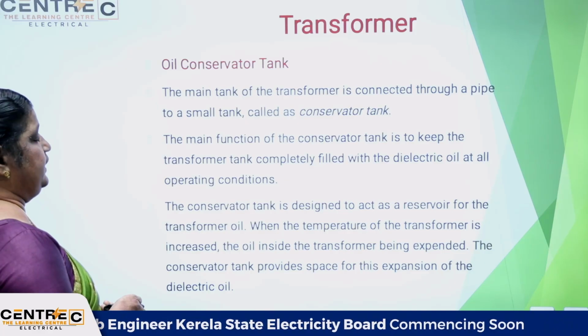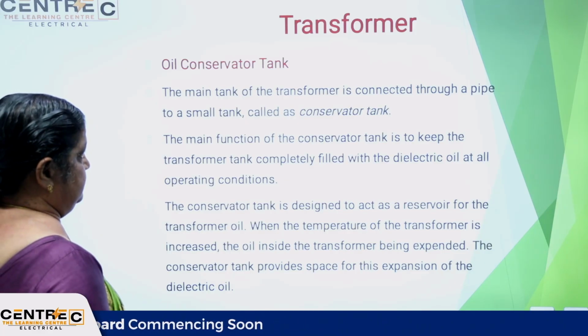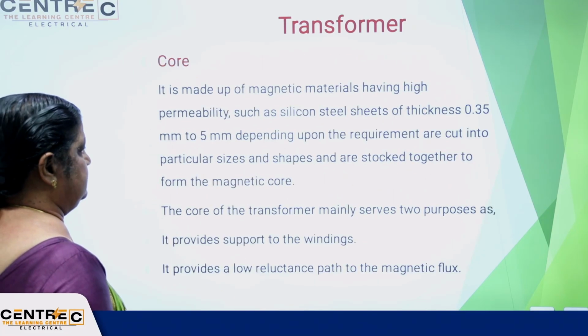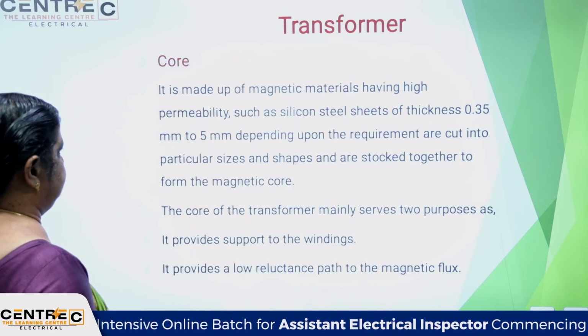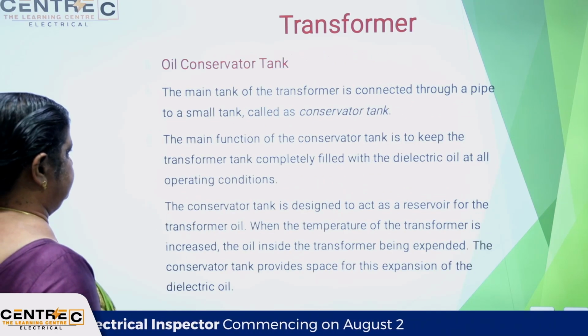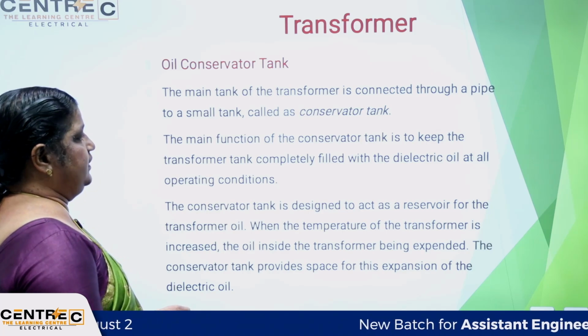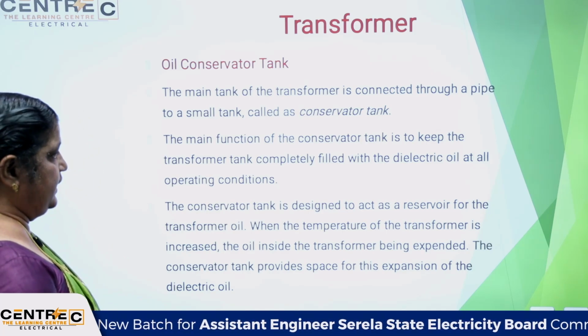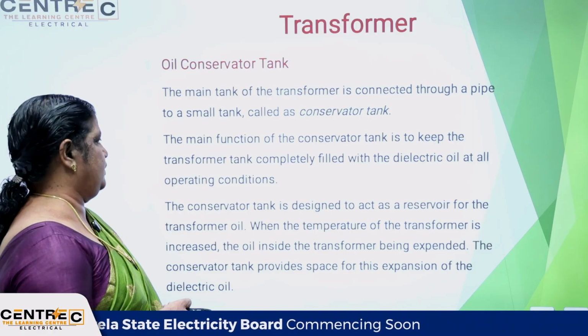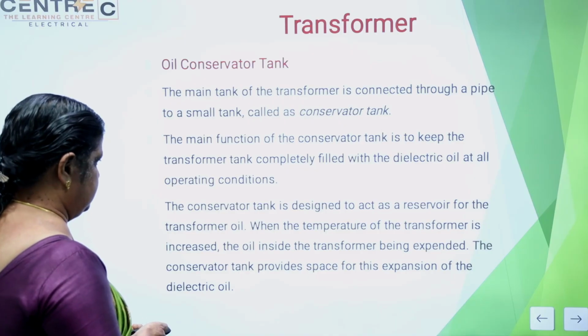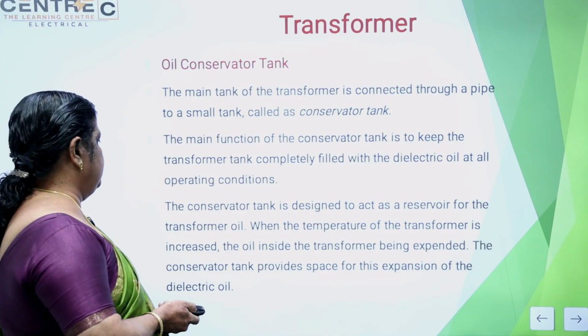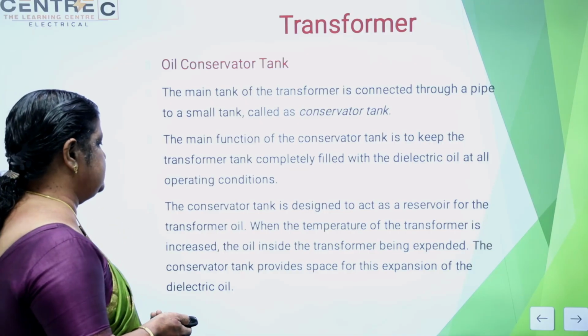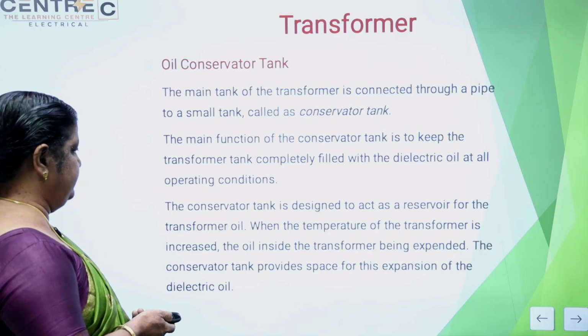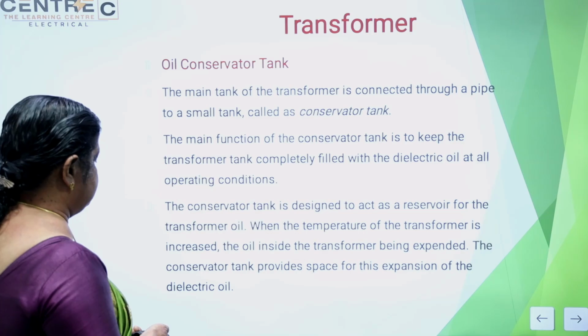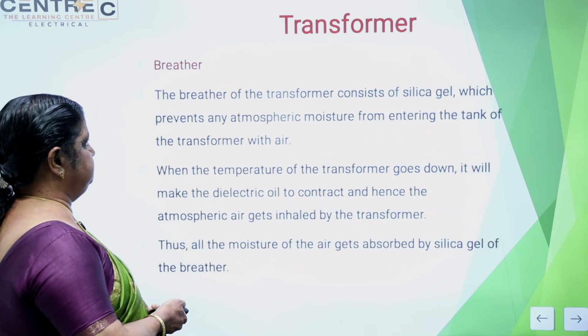Then the oil conservator tank. The main tank of the transformer is connected through a pipe to a small tank. This one is the transformer tank, then this is the main tank, connected through a pipe to a small tank called the conservator tank. The main function of the conservator tank is to keep the transformer tank completely filled with the dielectric oil under all operating conditions. The conservator tank is designed to act as a reservoir for the transformer oil. When the temperature of the transformer increases, the oil inside expands, and the conservator tank provides a space for this expansion of the dielectric oil.